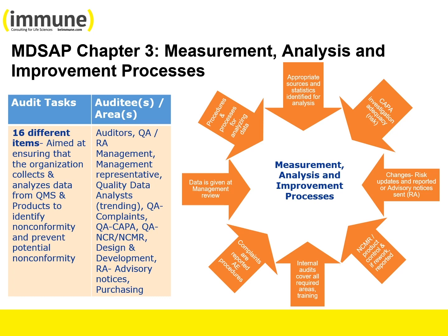This is to get a process overview and so that the auditor can understand management's knowledge and understanding of the processes. Information regarding device or identified QMS nonconformities observed during this portion of the audit is used to make a decision during the design and development chapters. It's also used to assess which suppliers could be potential focus for Chapter 7 and purchasing processes.